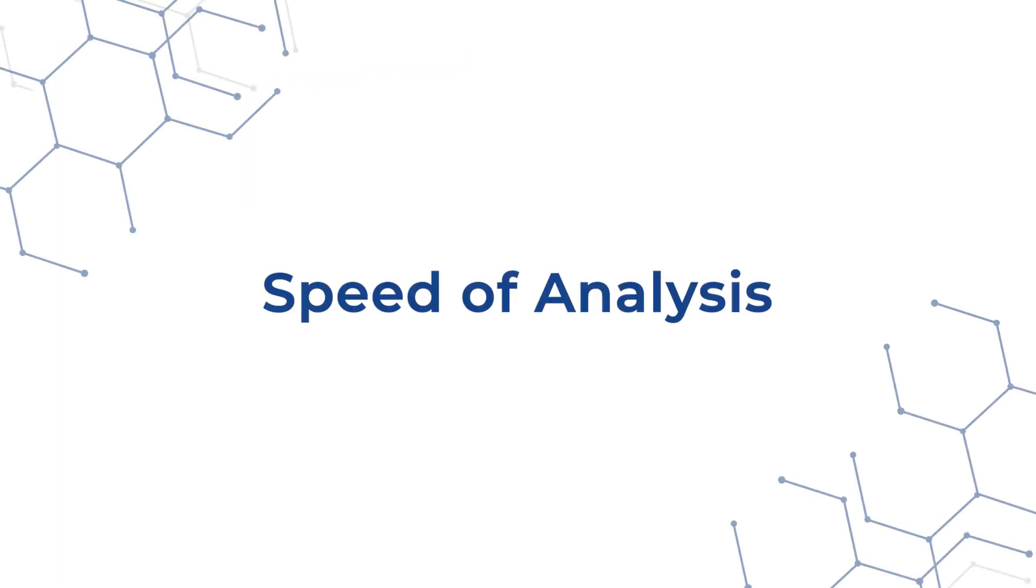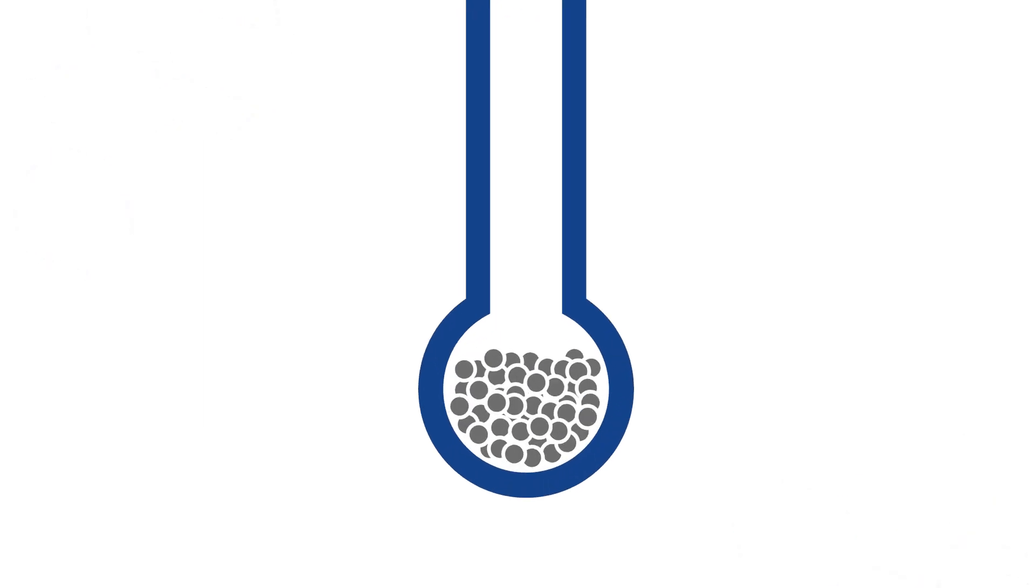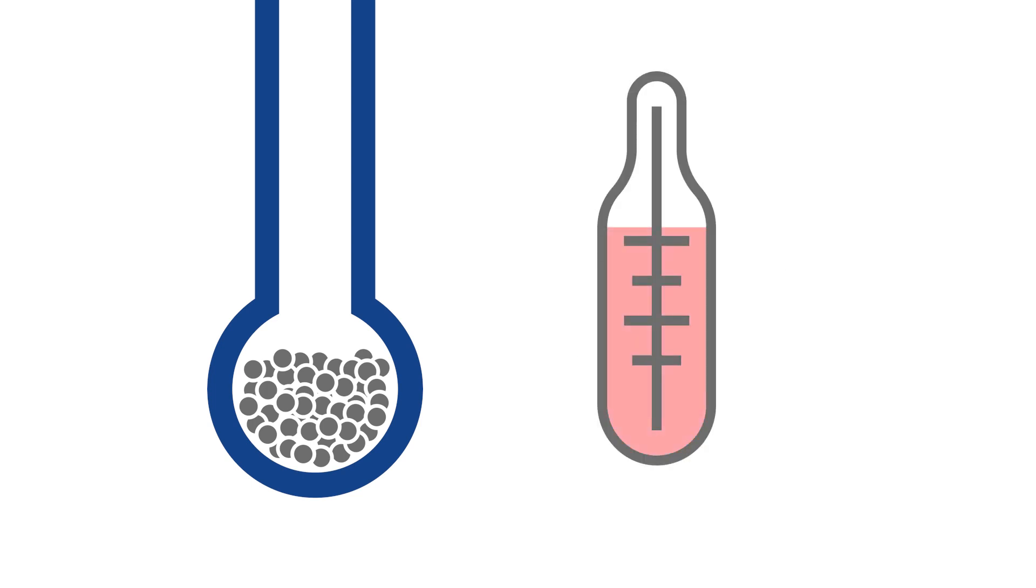These examples lead to another factor to consider, which is speed of analysis. Does the sample size affect the speed? The answer is yes. The higher the total surface area, the slower the analysis will be due to thermal equilibration having to reach first before pressure equilibration.